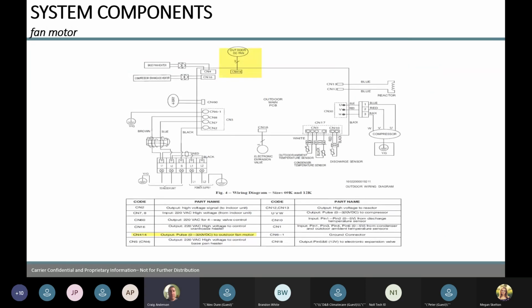Fan motor, similar to the compressor, all that. We can check the resistance to it. We can check the pulsing voltage going to the motor on the board on our CN14. We're checking the motor circuit. We're looking for a pulsing DC voltage to that fan motor to make it turn. As I said, it's all in the manual, and it's going to tell you what CN14 is doing, or it's going to tell you in the wiring diagram on the unit.